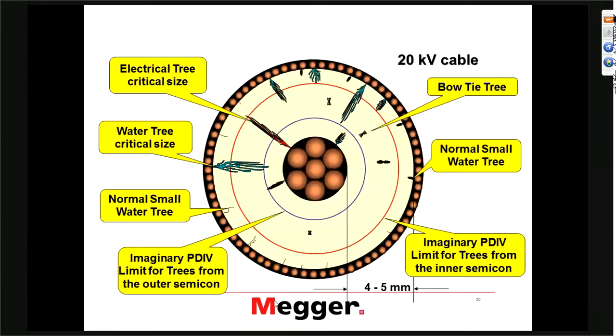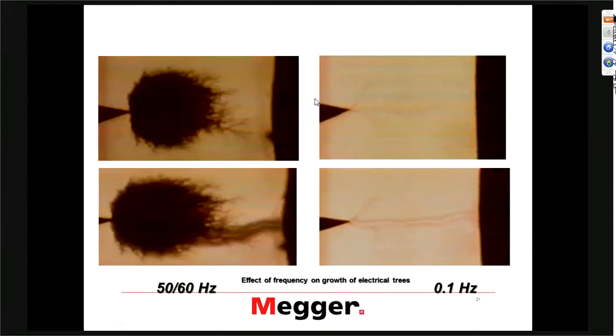The small trees are not affected, but that's why we say that a service-age cable where you have this large tree and you do a VLF test, you bring it to fruition. Once this is done, you have the small ones — small today, but in three or four years they could have reached a longer length and become now a critical thing. That's why you might want to retest the cable after some period of time.